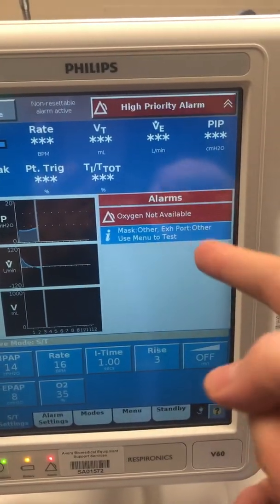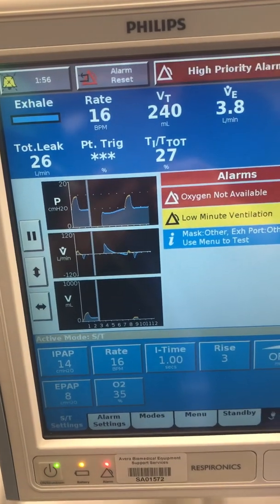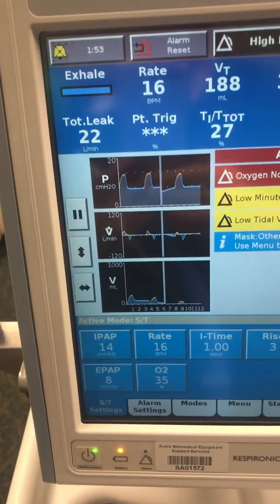This top piece is what's going to go to the patient through the mask, and then this right here is an exhalation valve. So I'll go ahead and attach my test lung here to my patient circuit, and then we'll turn it on using the interface. To do that, we're just going to push the power button, and then the screen will turn on. My alarms are telling me right now that I don't have oxygen available, which we know because I did not put oxygen on.